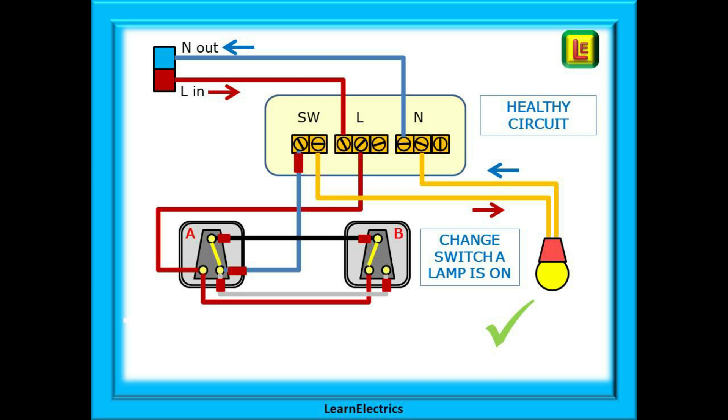This time we will change switch A over. The electric comes from the live loop to switch A on the first brown wire and then travels to switch B on the second brown wire. It goes through switch B to the black wire, along the black wire back to switch A, through switch A to the blue phase wire and up this blue phase wire to the switch block, along the pendant wires to the lamp, back to the neutral block and out on the neutral wires. A complete circuit so the lamp lights up. So easy when it works correctly.